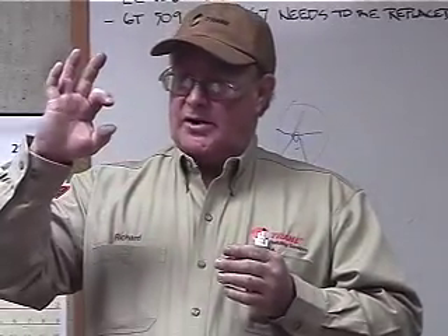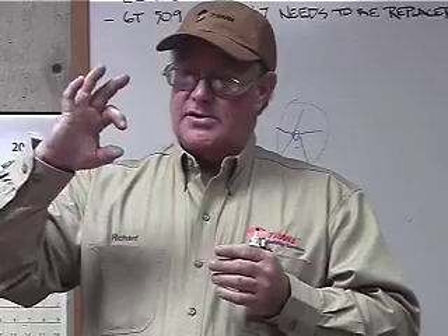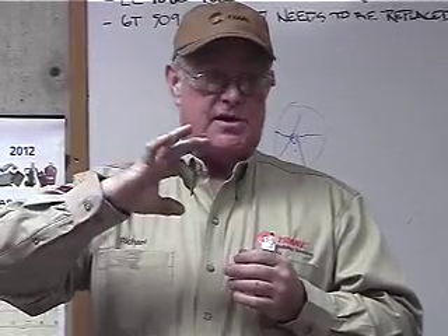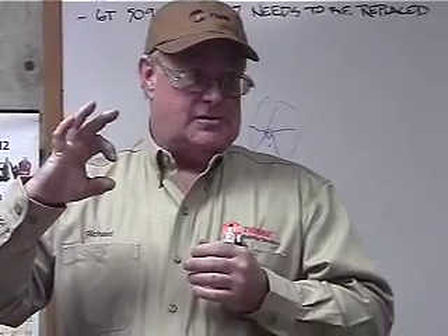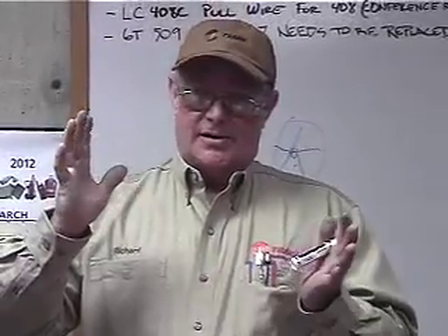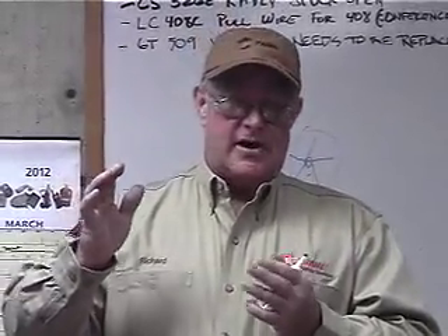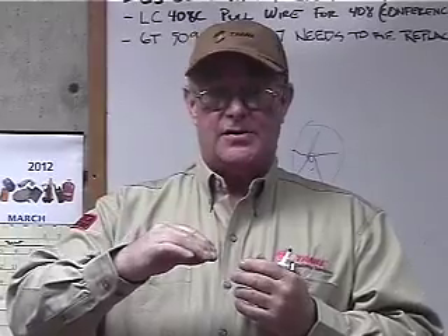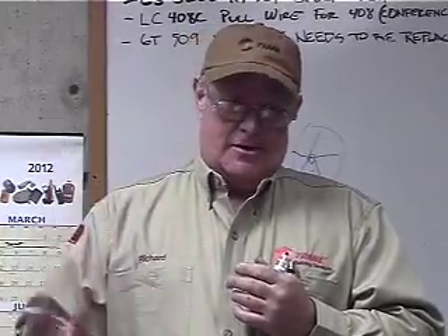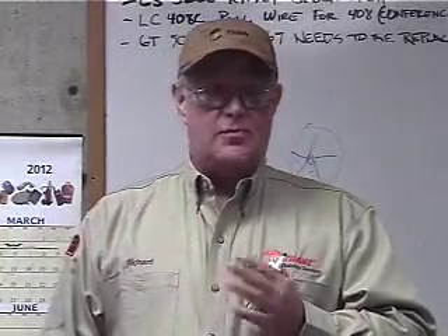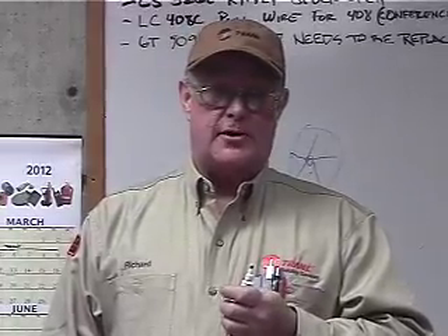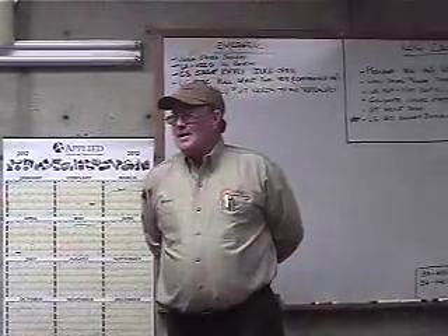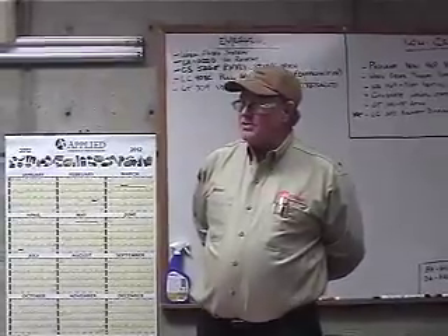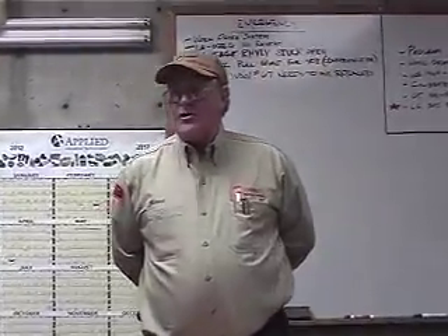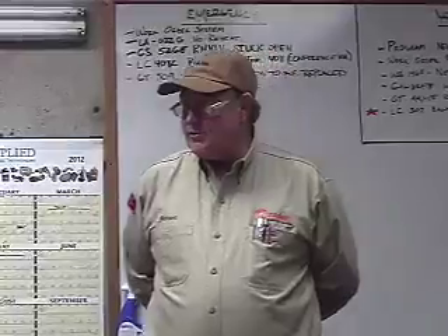But you'll see a little pressure gauge on there, and it'll start reading what the pressure is inside the vessel. So if your chiller's at a negative 8 inches of vacuum, it's going to show a negative 8 inches. Or if it's at 6 psi, it'll show whatever's happening in the evaporator. Okay, I was asked to come back in and see if I can answer some questions as far as maintenance, or if you encounter some problems on your chillers.